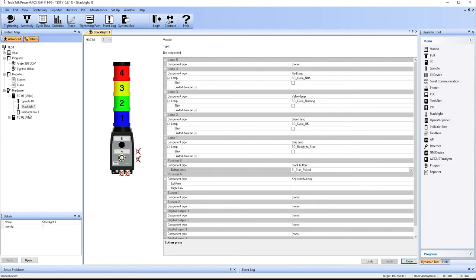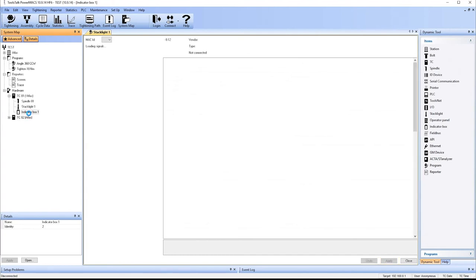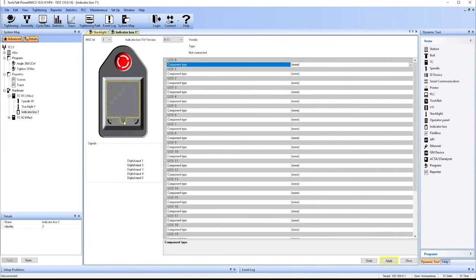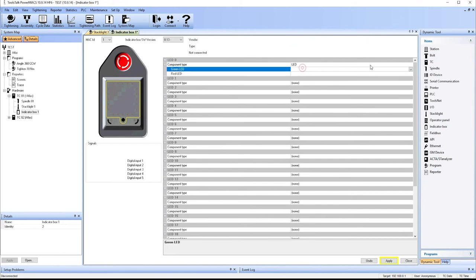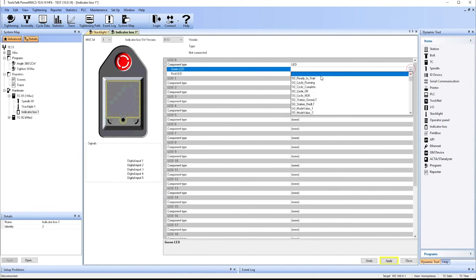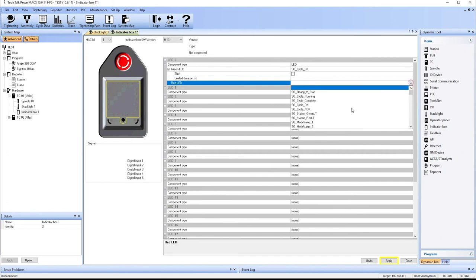We can also set up our indicator box. So here's where we would define what the lights in the indicator box mean. To do that, we've got to be at a version 13 at least of the indicator box. But then we can simply click on the indicator box. Tell it that it's an LED. And tell it what the green LED is going to represent. So in this case, it's going to represent cycle okay. And a red LED is going to indicate cycle not okay.